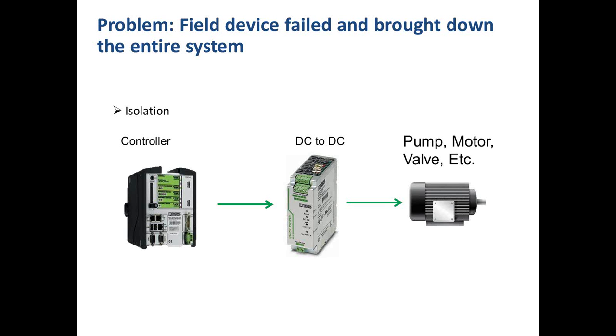DC to DC power supplies are also important to a reliable power system design. They have certain perennial jobs. In this example, galvanic isolation is the functionality. Quite commonly, a load is powered from the same supply as the controller. If the load draws too much current or shorts completely, there will be a complete loss of control. Adding a DC to DC between the controller and the load ensures that this situation is no longer possible. If the load shorts, the DC to DC will alarm and report the failing device to the control system.